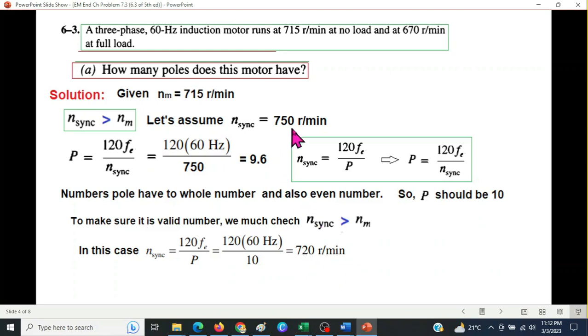So we have assumed 750, but when we take the number of poles to be 10, it comes to be 720 revolutions per minute. And this still is greater than 715 of the rotor speed. So this is greater than 715 and therefore our selection of the pole is correct. So finally we can say that the number of poles is equal to 10.